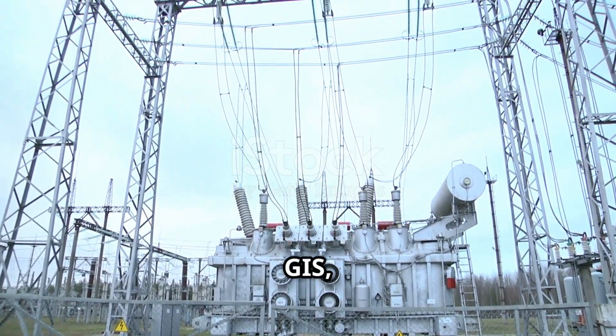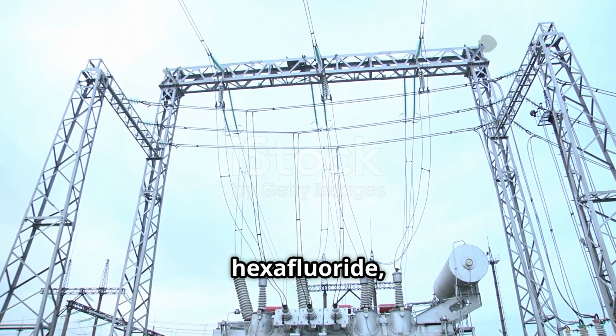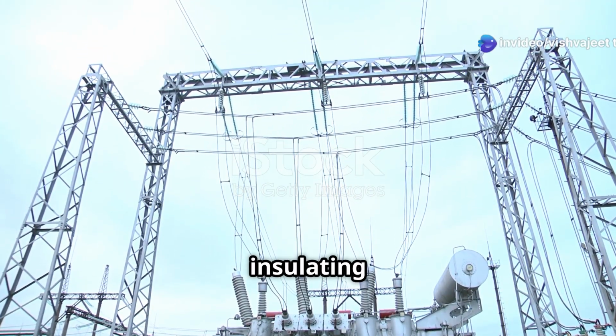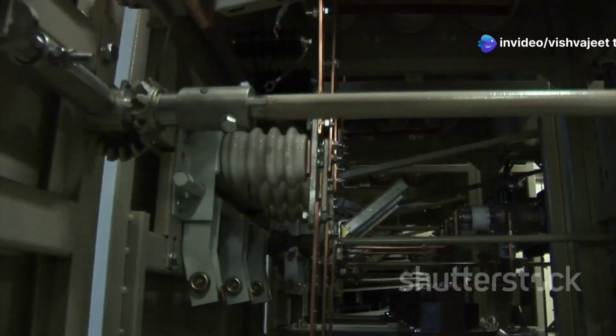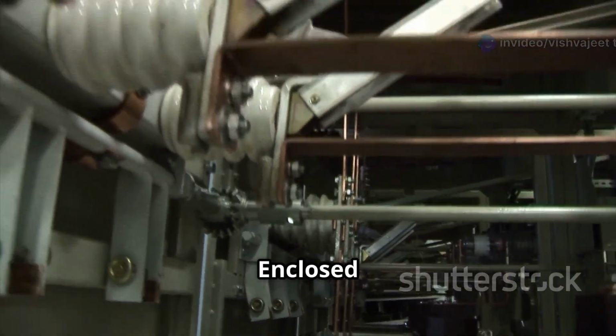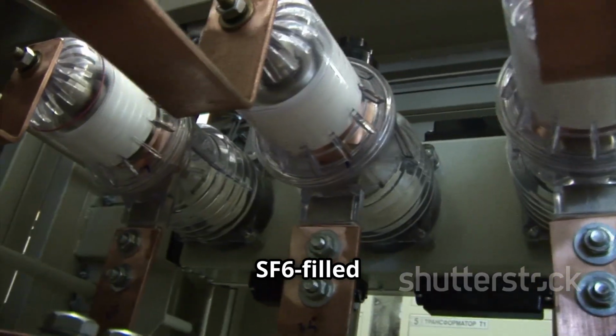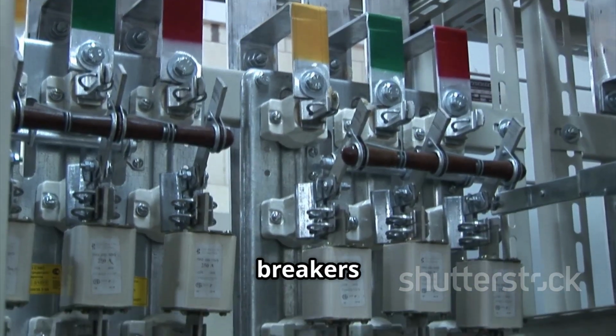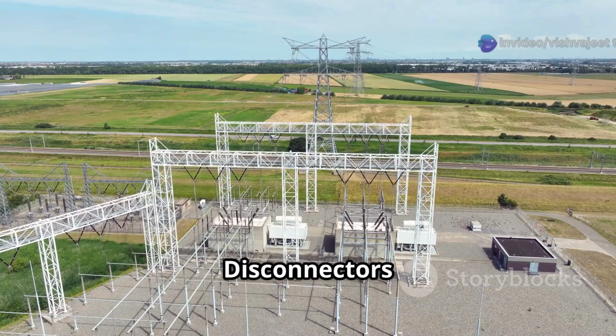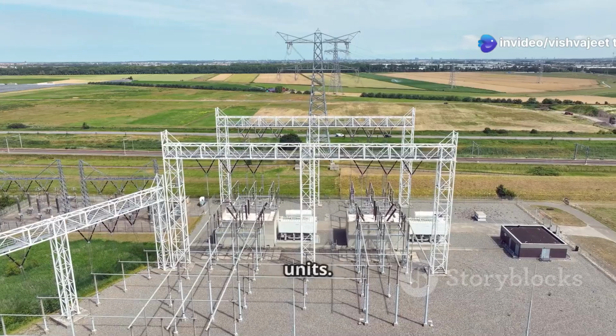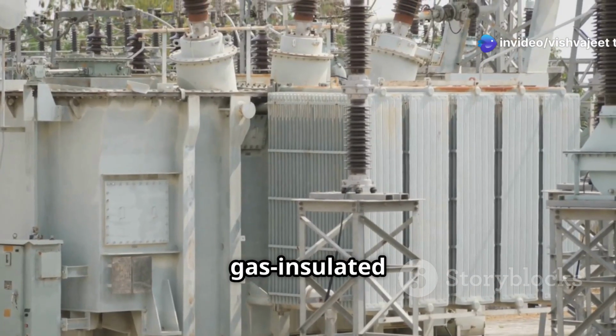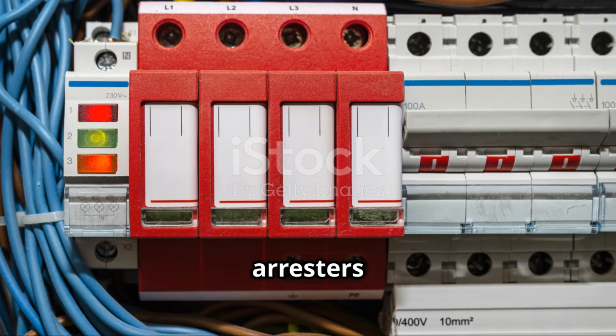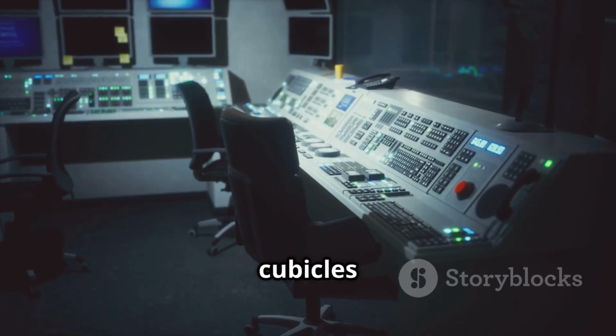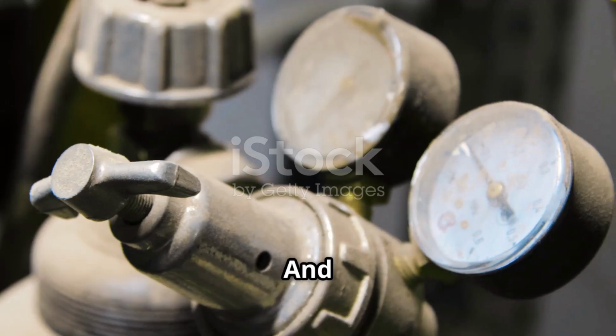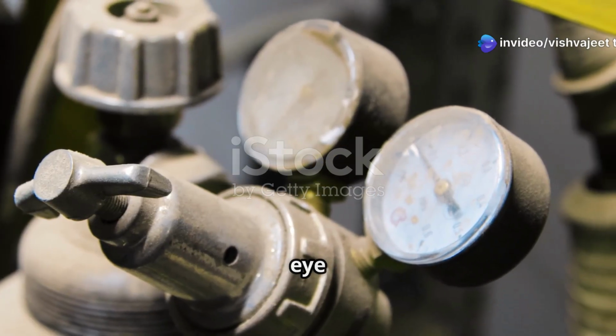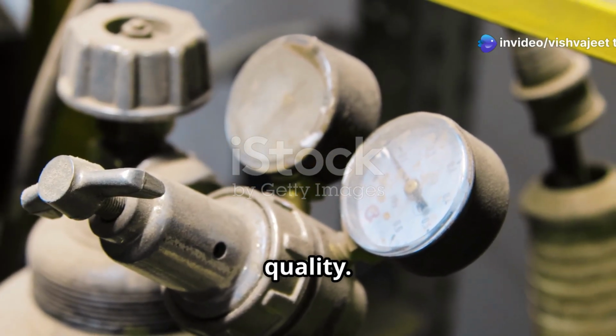Gas-insulated substations, or GIS, use pressurized sulfur hexafluoride SF6 gas as the primary insulating medium within sealed metal enclosures. Enclosed busbars are housed in SF6-filled tubes. SF6 circuit breakers feature a compact design. Disconnectors and earthing switches come as enclosed units. In some designs you will find gas-insulated transformers. Surge arresters are often integrated. Control cubicles are used for monitoring and operation. And finally, the gas monitoring system keeps an eye on SF6 pressure and quality.